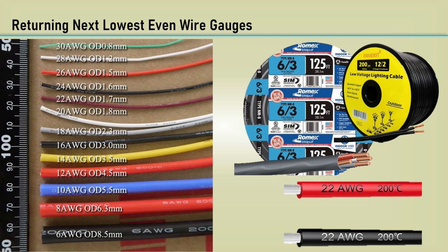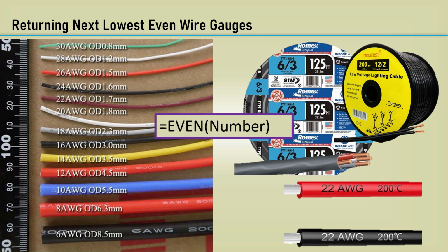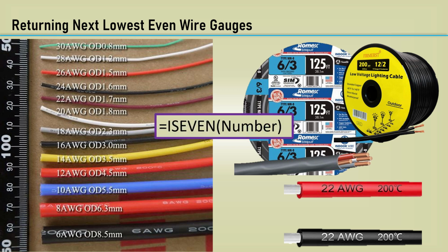Excel has an EVEN function. The problem is it returns a number rounded up to the nearest even integer. We need to round up to the next larger diameter, so we need to round down to the next even gauge. The function does us no good. We can simply check the calculated gauge with the ISEVEN function. If it's true, we return the rounded gauge. If not, we just subtract one.